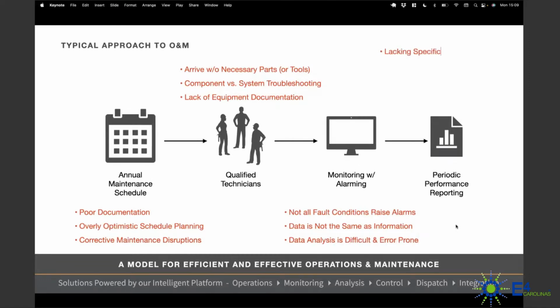Unfortunately, because of all that variation, remote operation, and late ownership, this doesn't come together necessarily as well as people would hope. That transition out of construction and commissioning to the O&M provider usually lacks what we would call good, solid documentation. The actual maintenance schedule itself is usually overly optimistic when you consider that you have plants spread out all over, sometimes multiple states. When technicians, even if they're very skilled and knowledgeable, arrive at sites, they usually don't have the information they need to really understand what is going on. So they spend time hunting around, looking for problems. They arrive without necessary parts or tools, and there's a lot of specialty parts and tools necessary for this different type of equipment. A lot of times we spend time troubleshooting components versus systems and how they're interacting with each other.